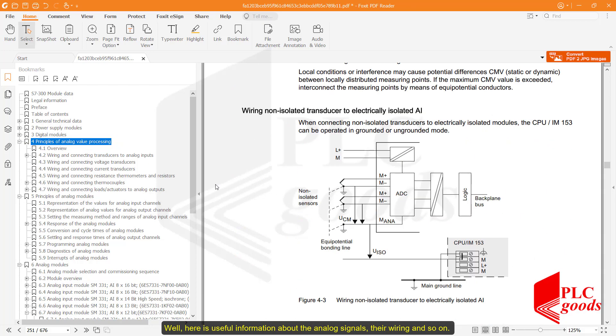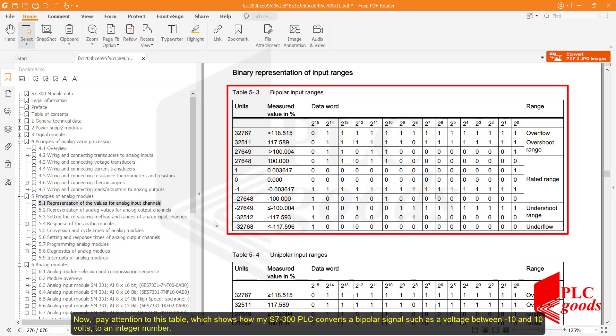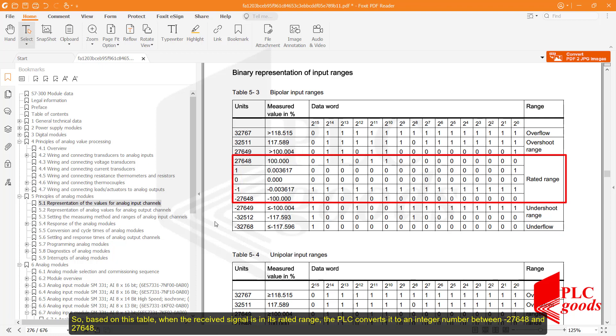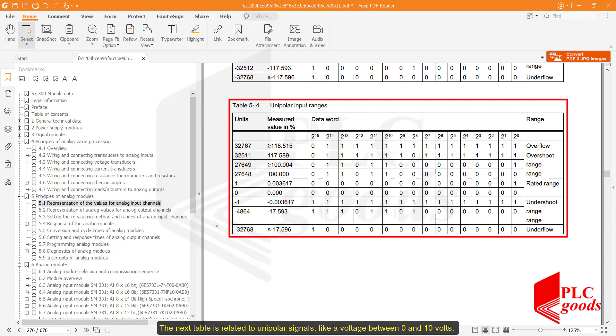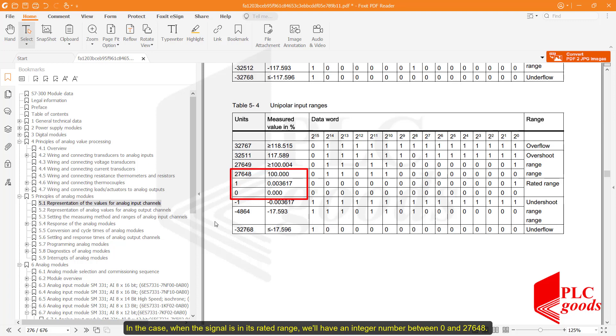Here is useful information about the analog signals, the wiring, and so on. This table shows how my S7-300 PLC converts a bipolar signal — such as a voltage between minus 10 and 10 volts — to an integer number. When the received signal is in its rated range, the PLC converts it to an integer number between minus 27,648 and 27,648. The next table is related to unipolar signals like a voltage between 0 and 10 volts; in this case the integer will be between 0 and 27,648.